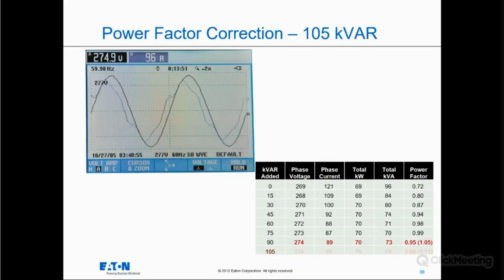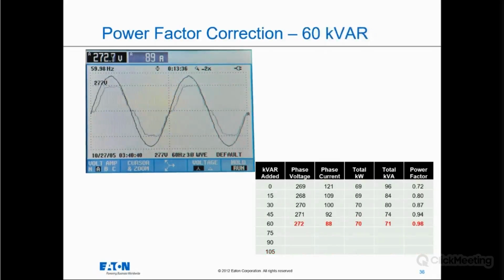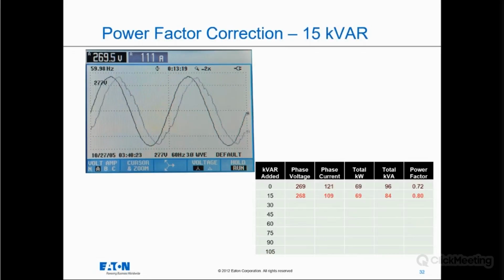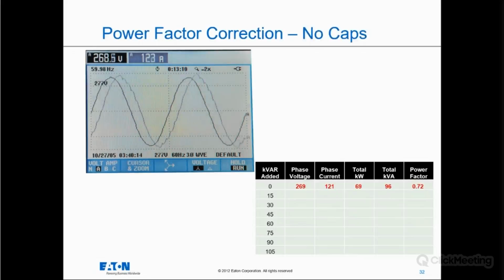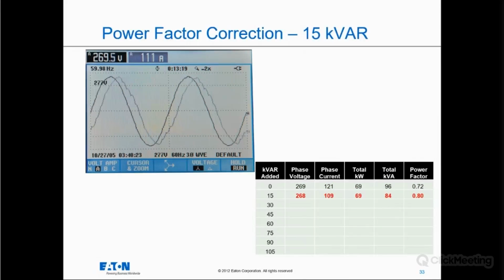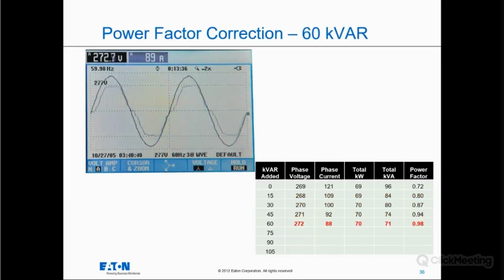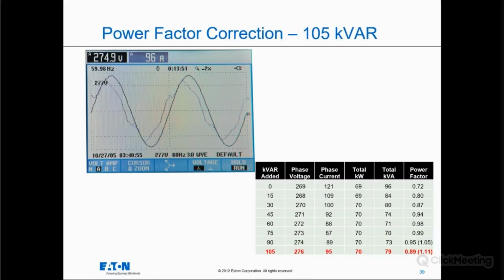I'm going to back up real quick and scroll through these so you can watch the waveform. You can see we're out of phase, but the current waveform looks pretty clean. It does have a couple notches in it, but as we add capacitors into the circuit and come into phase with each other, you can see that the waveform is getting more distorted as we bring on more capacitors. And certainly as we cross over into capacitive, it's getting even more distorted from adding capacitors to it and amplifying some of the harmonics that may be present on this system.